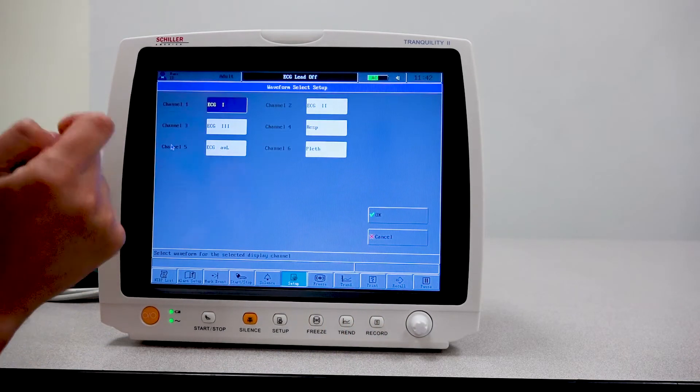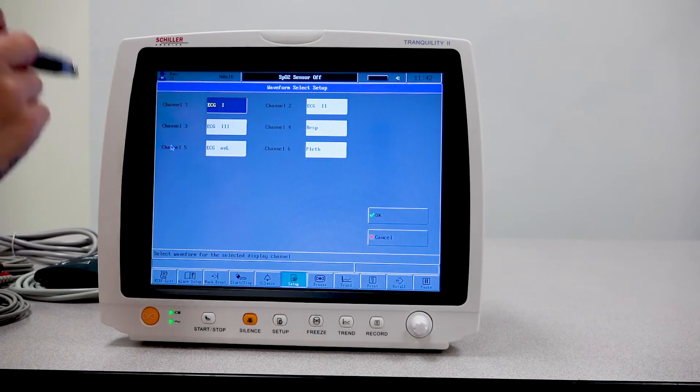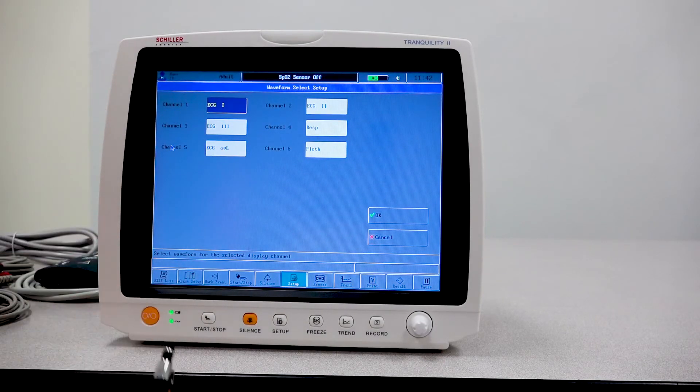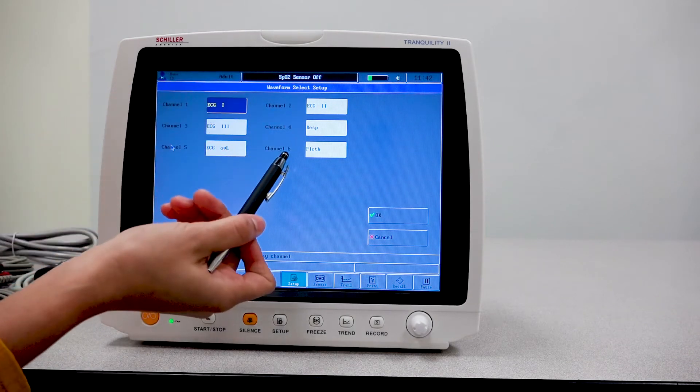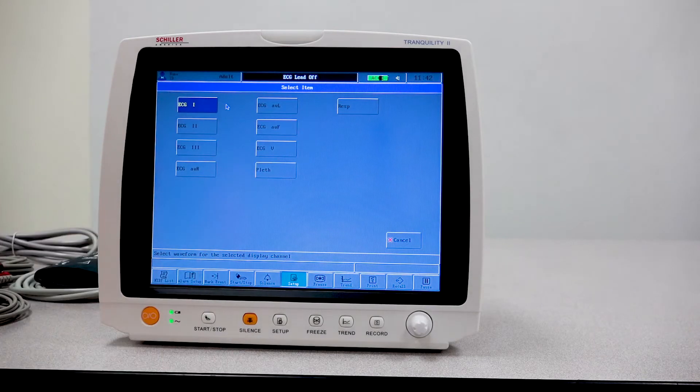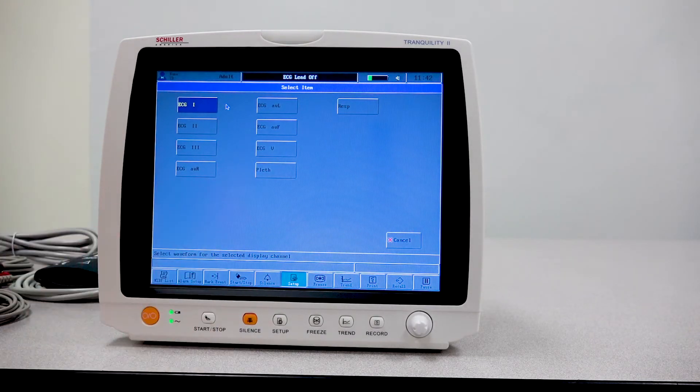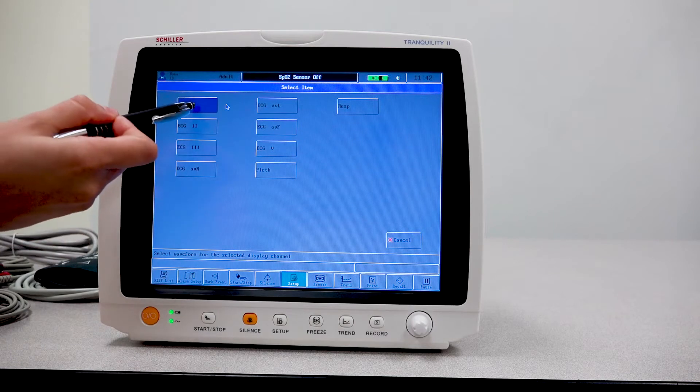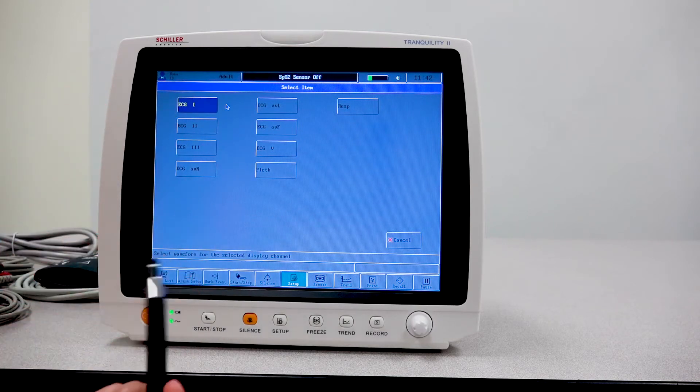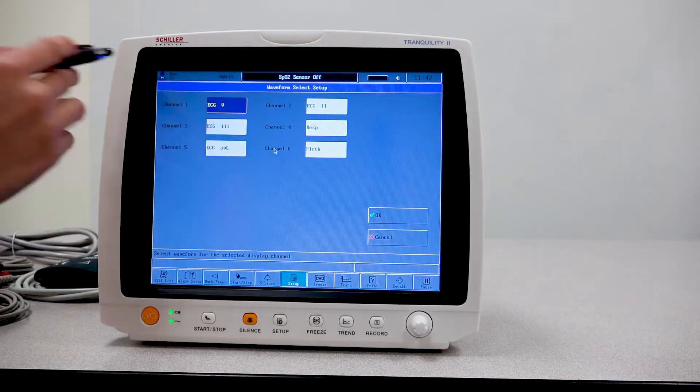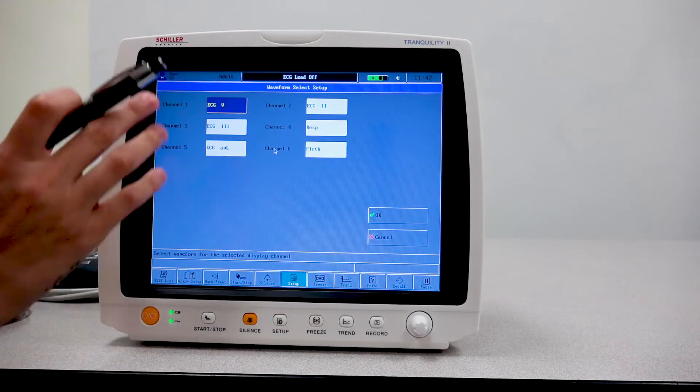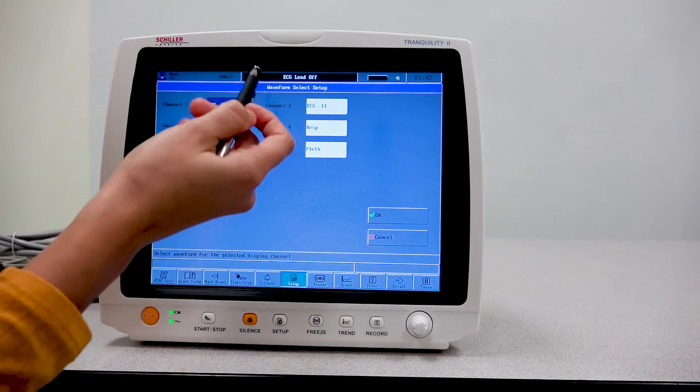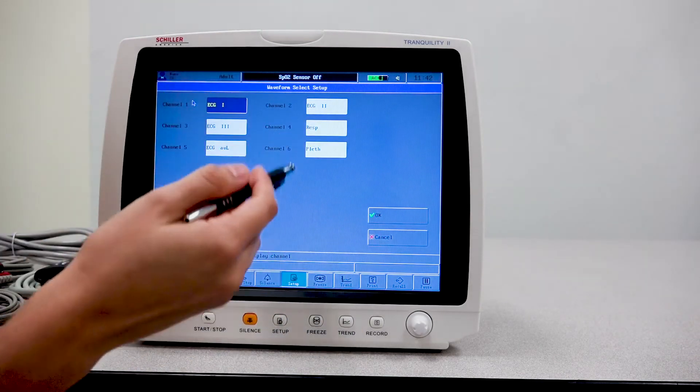You then have your waveform selection. This is pretty much on your main screen, the different waveforms that are being showed. You have your channel one through channel six. And in each channel, you can select what you want to see. So if I wanted to change my ECG lead one to let's say ECG lead V, I can go ahead and do so. And now my channel one will show that particular waveform.